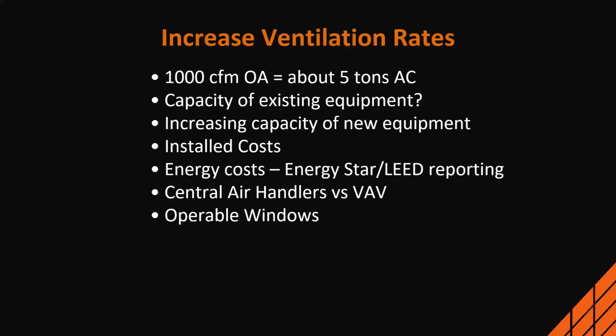Or the other option is you increase the discharge temperature. So instead of being 55, you raise it to maybe 60 degrees. So it takes longer for those VAV boxes to satisfy the space, and so we deliver a little bit more air. If you have a building, maybe a school building or something like that with operable windows, that's very effective also. The longer you can leave those windows open and get natural ventilation through your space, that's also going to be very effective.